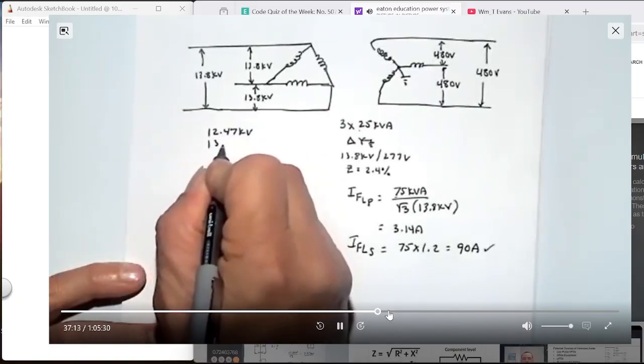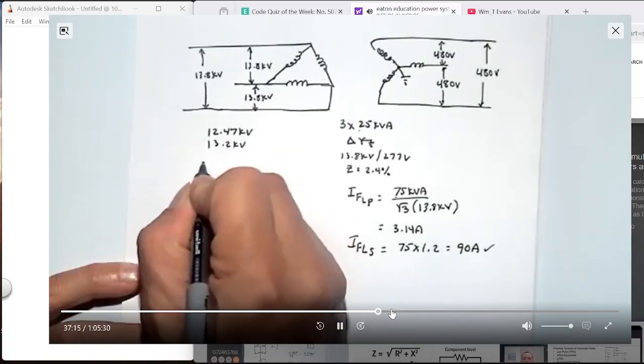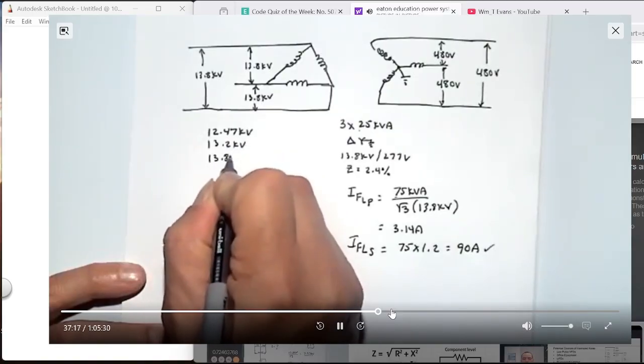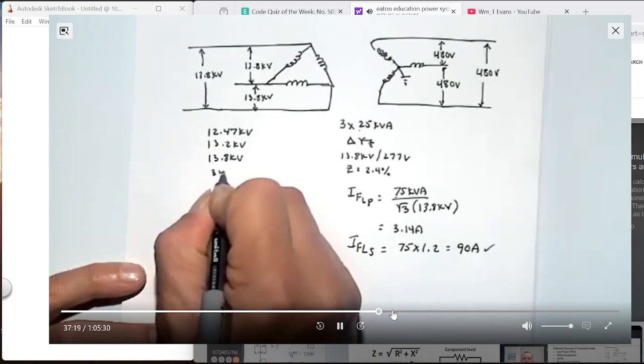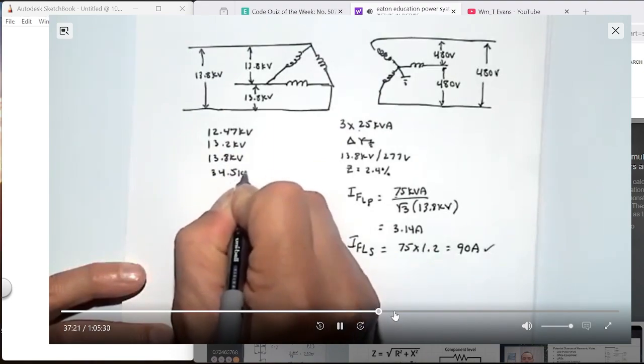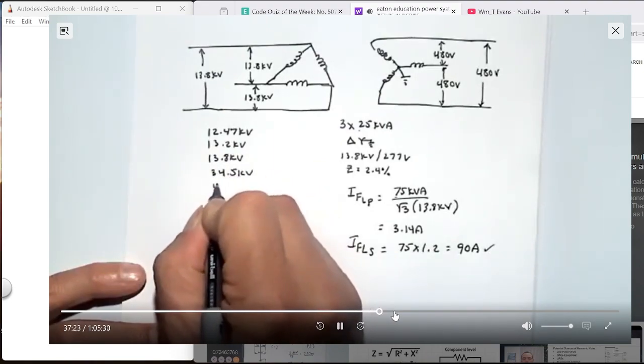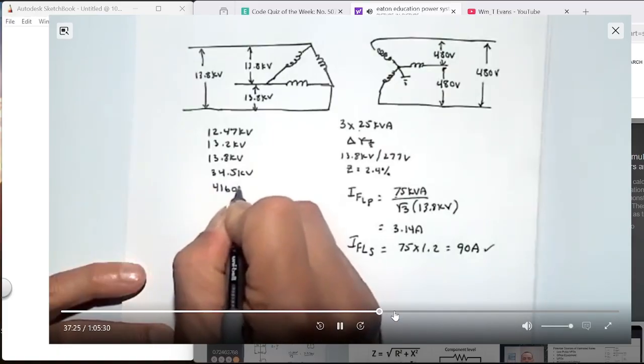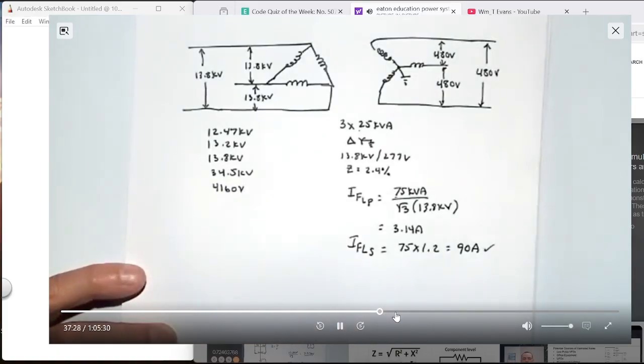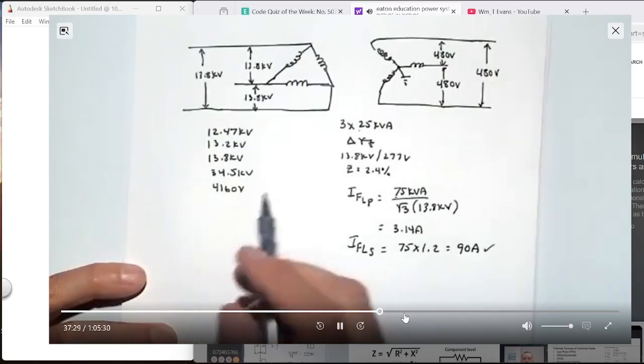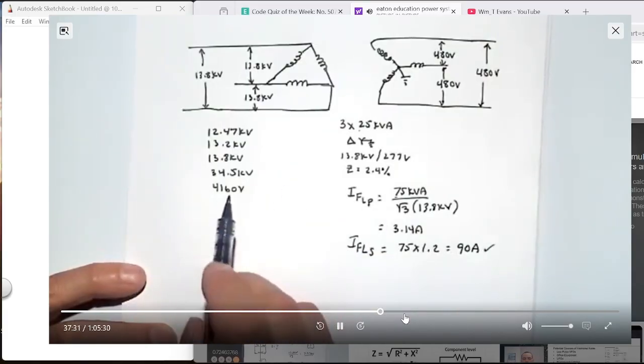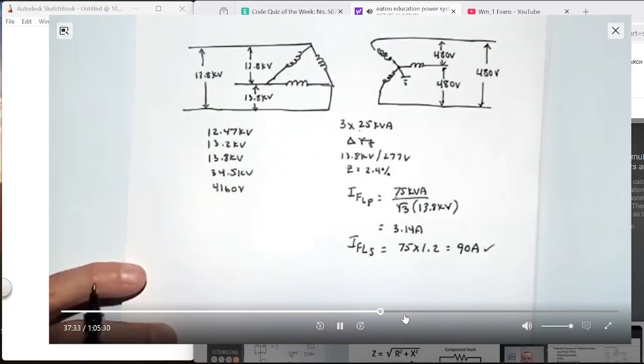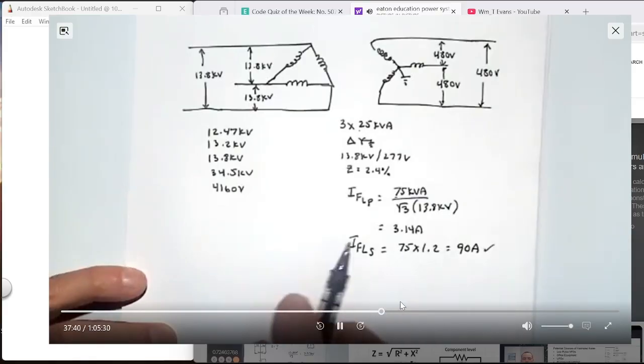I could use 13.2 kV. I could use 13.8. I may even go as high as 34.5 kV for medium voltage, and I might go as low as maybe 4160 volts or 4.16 kV. But anyway, or even 2.4 kV. But the point is, I'm trying to be consistent, so I'm using the 13.8 for this calculation. So again, you can see what our load currents are going to be, primary and secondary.